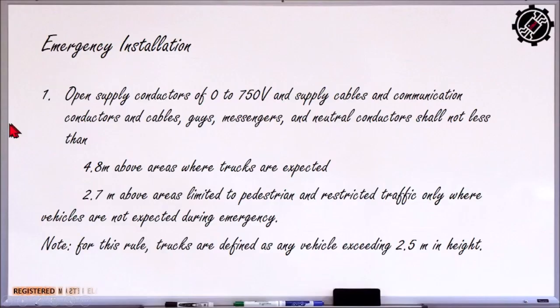Okay, so if you have an emergency installation, ito, so open supply conductors of 0 to 750 volts and supply cables and communication conductors and cables, including the guys, the messenger wires, and the neutral conductor shall not be less than, so yung mga measure. First, you have 4.8 meters above areas where trucks are expected. No? So, for example, if may i-install tayo na linya for emergency purposes, no? So, kailangan na nating lagyan ng power, no?